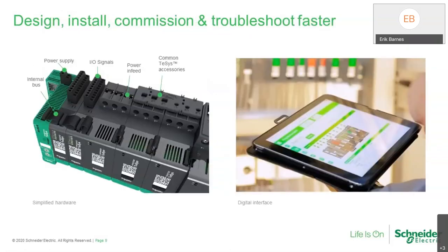It has a little bit different structure in how you wire it. So the picture on the left here shows the island mounted on a DIN rail, and the control wiring. You remember before we had that diagram with wires running around everywhere. Well, all that kind of goes away. So now when you want to do your control wiring with TeSys Island, you're going to mount this on DIN rail, and each island module has a ribbon cable attached to it. Then you mount all the devices on the DIN rail, and you attach that ribbon cable to the adjacent device with a click. So click, click, click, click, click. You make your communication cable connection to your PLC, and there's your control wiring. So it's that simple. It's that easy.